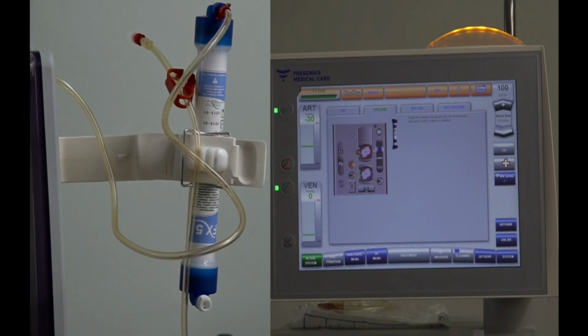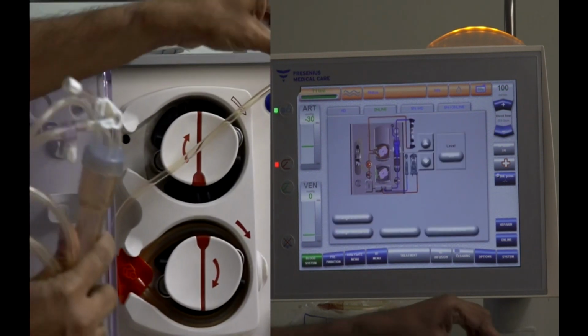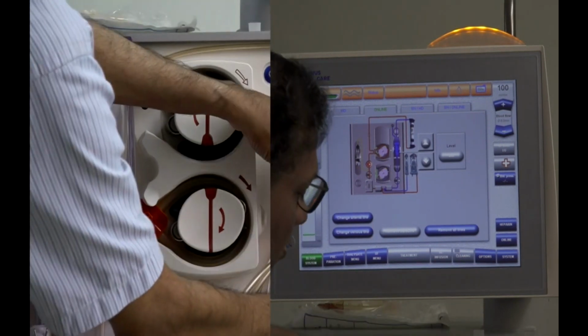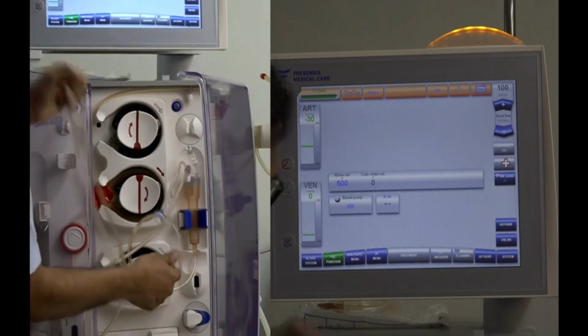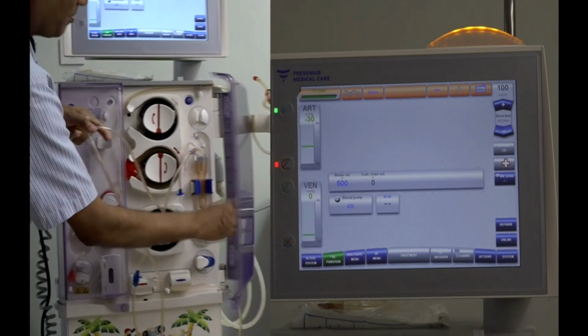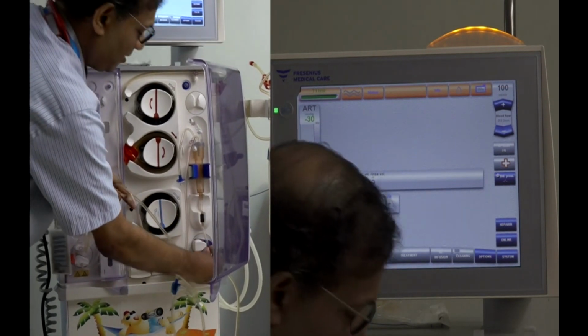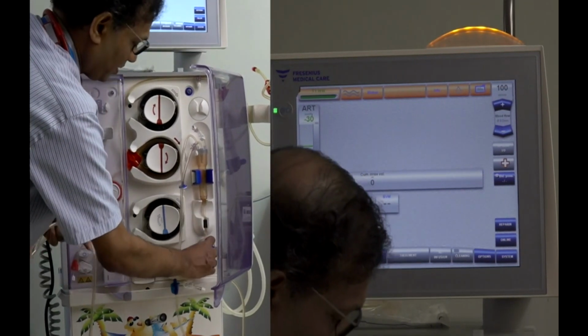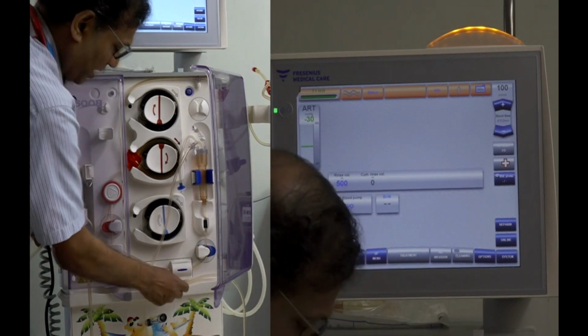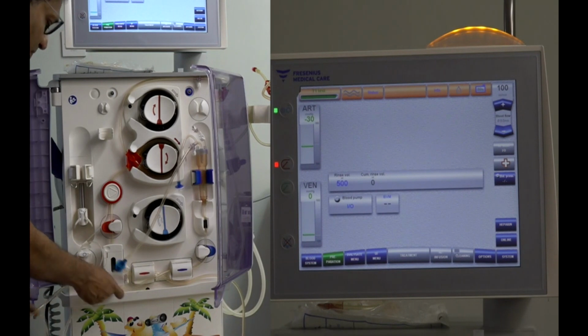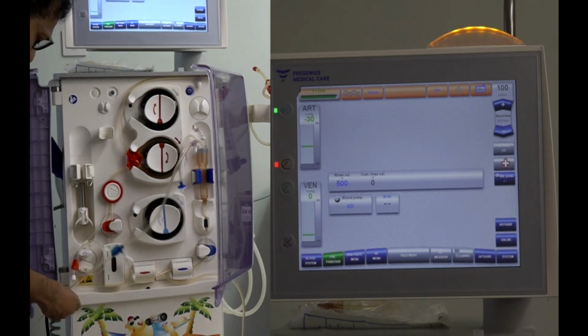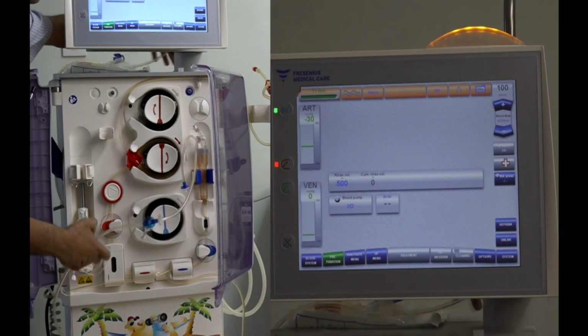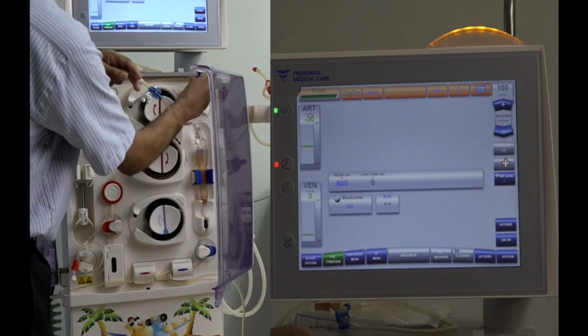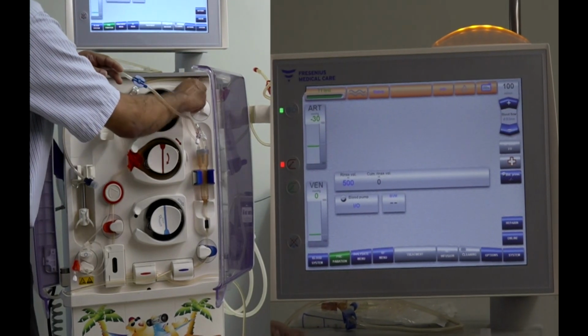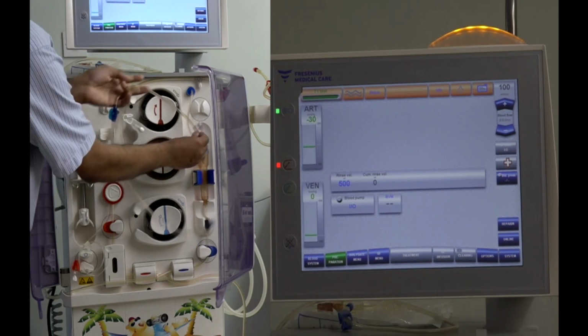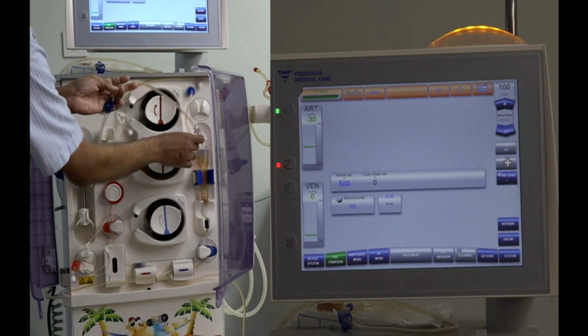The pump started and drew in the arterial line, and now we are ready to load the venous line. The venous line, I'll start with the venous bubble chamber. This is the optical detector segment. This is the venous line clamp. This is the blood temperature sensor. This is the venous pressure transducer protector. It's built in on this set, and this port is for delivery of substitution fluid post filter.